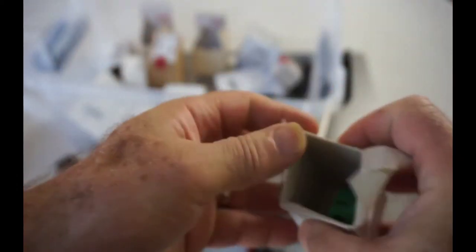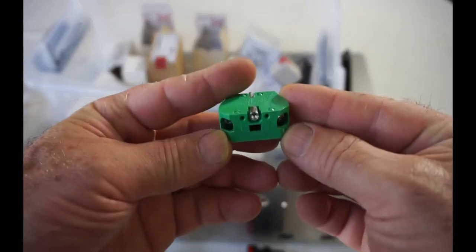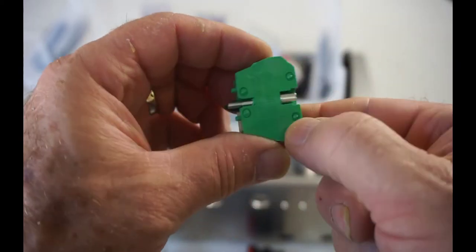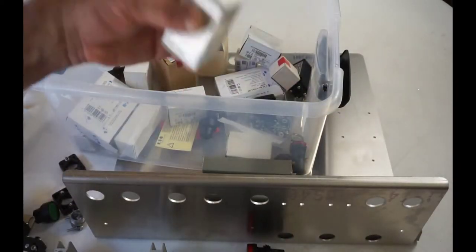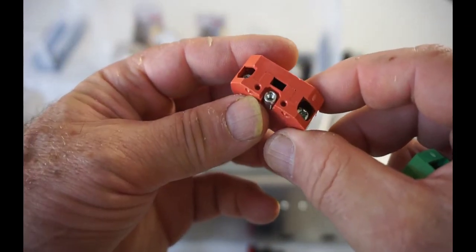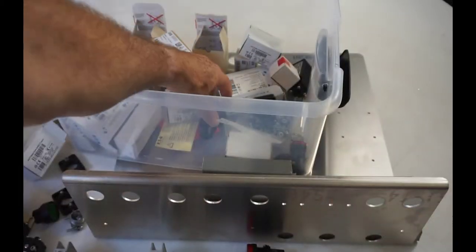We've got a lot of different components here. We've got a normally open contact block. With this manufacturer, normally open contacts are green and you have two sets, two terminals here, and it's a set of normally open contacts between them. I should open up another one and here's a red one. On this, the red one indicates normally closed with this manufacturer.